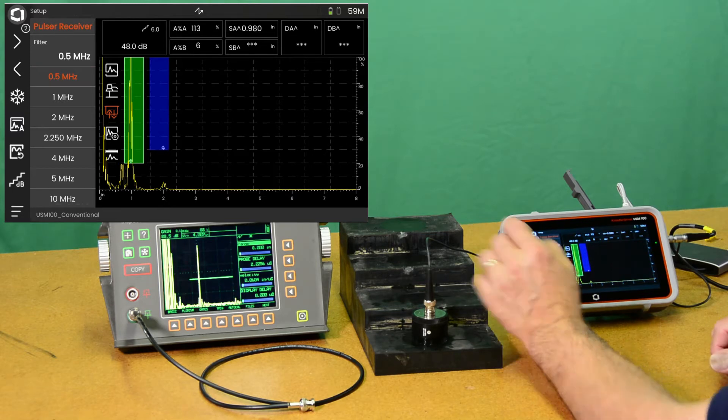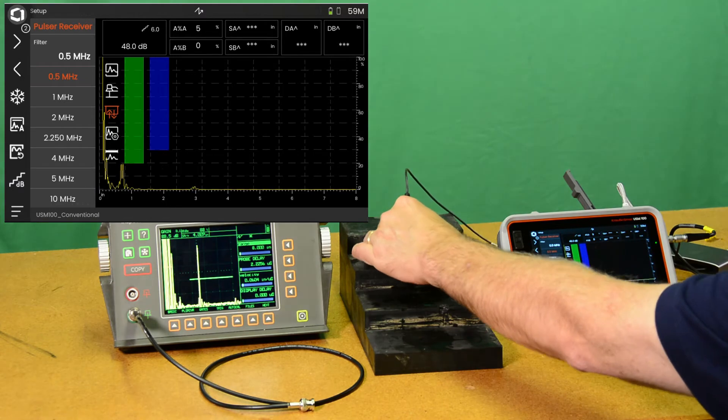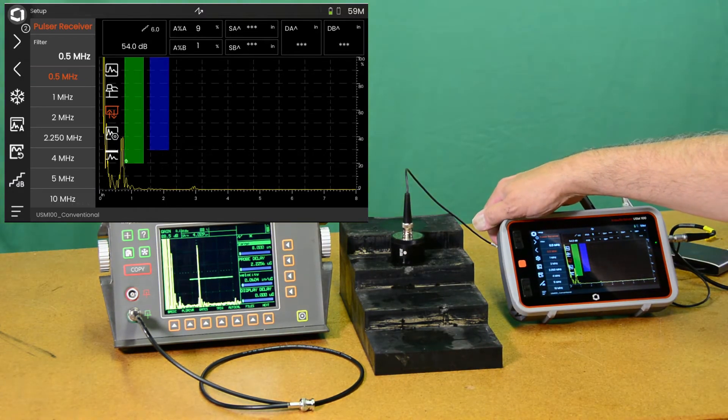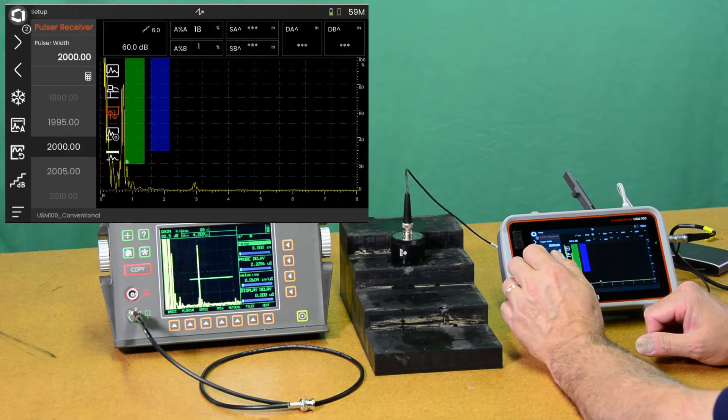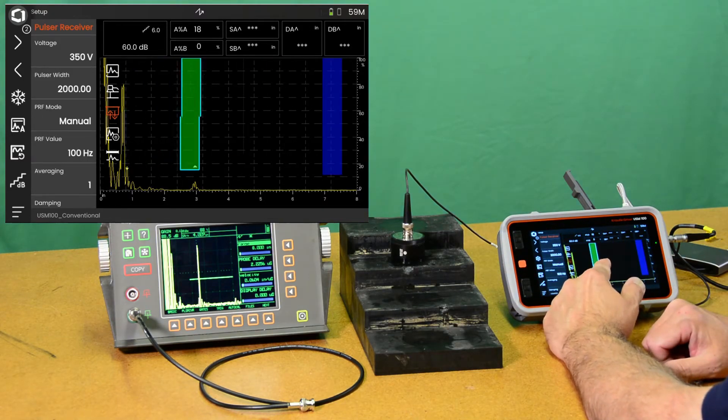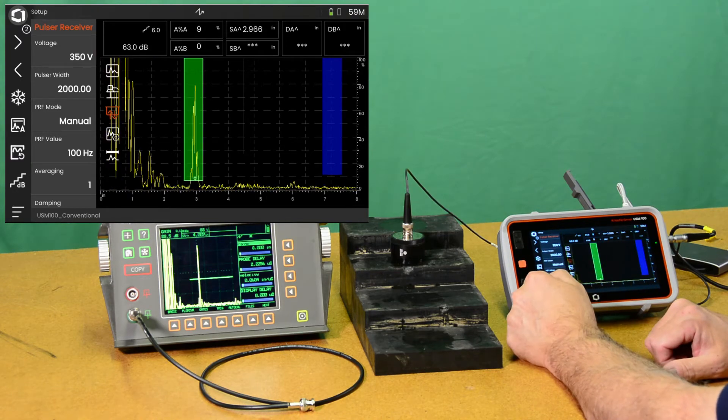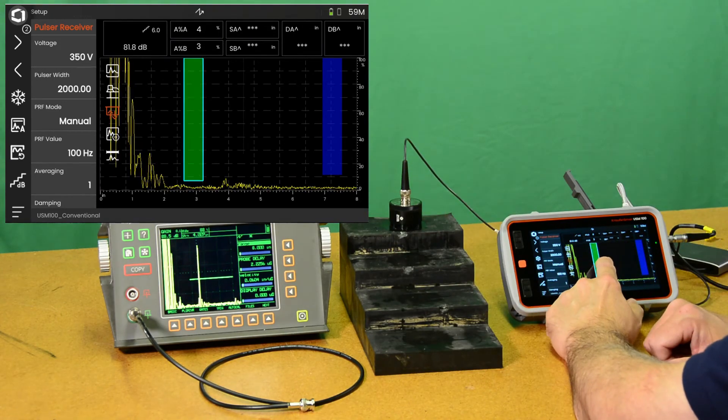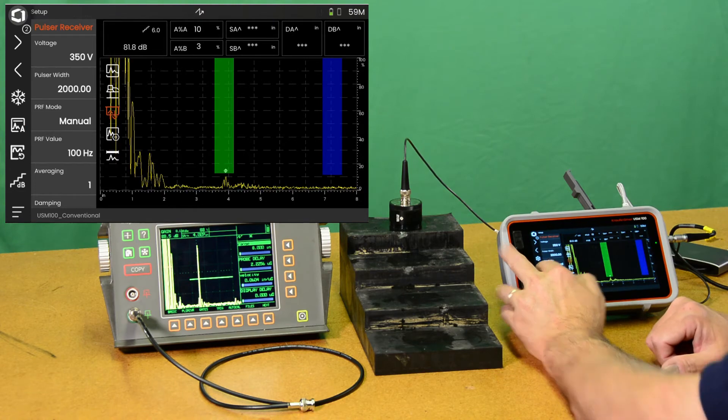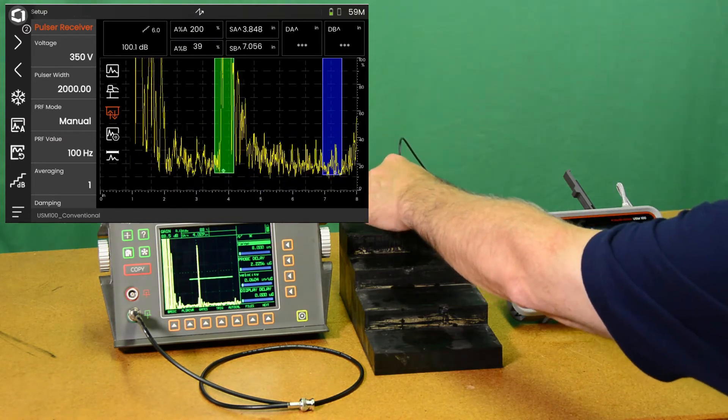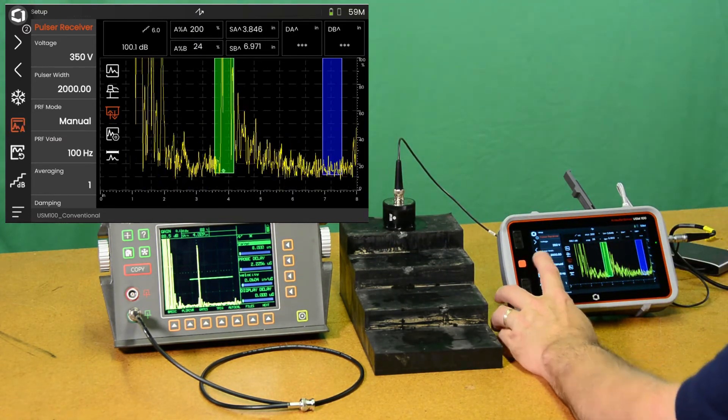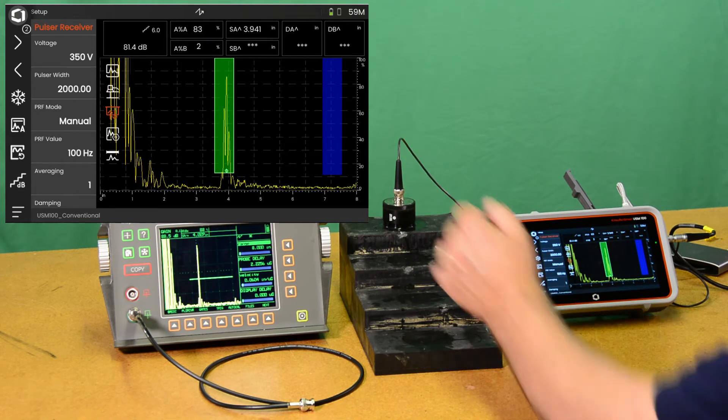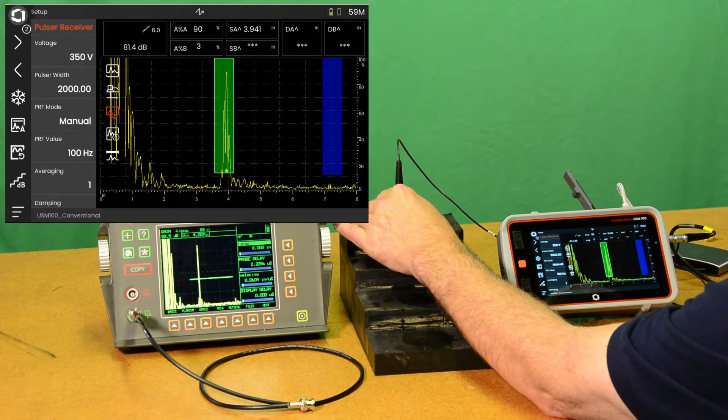Okay, so we have our one inch, two inch, three inch. Let's give it a little bit more gain. Get our B gate out of the way and drag our A gate over here. Let's go auto 80. And our four inch step. Auto 80. I think we have very good coupling here. We're way high. Let's hit auto 80 again. Now we're back to about 81 dB. Nice quiet noise floor.